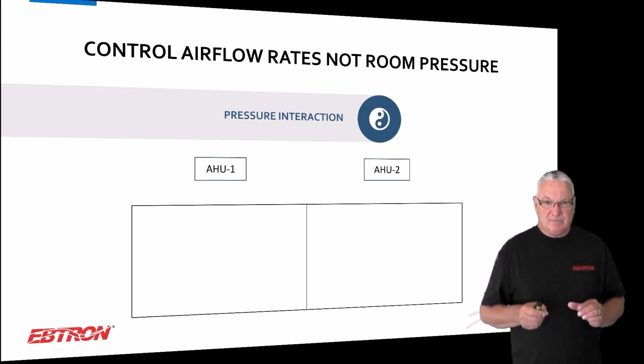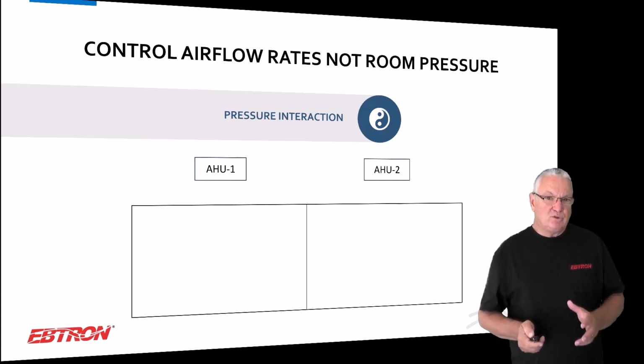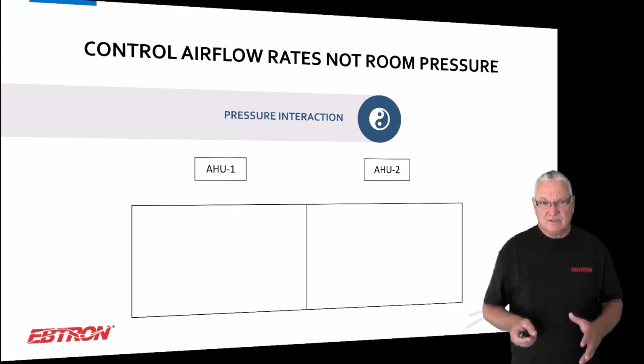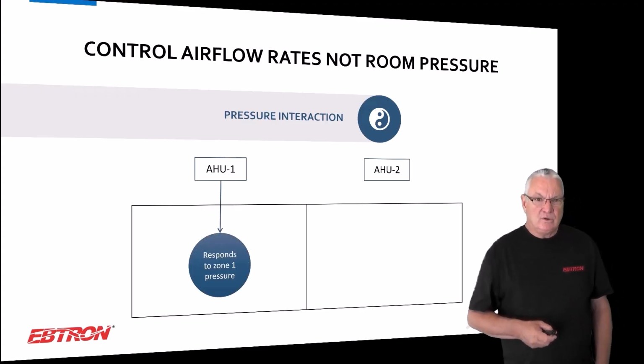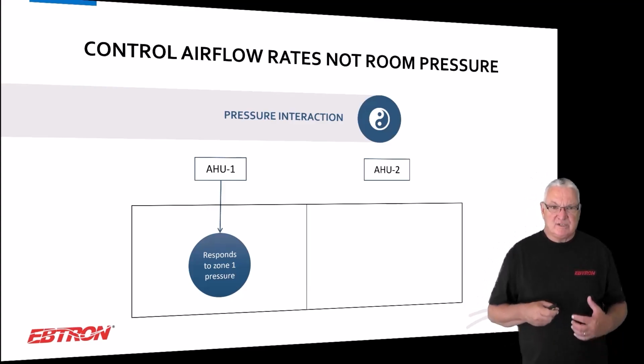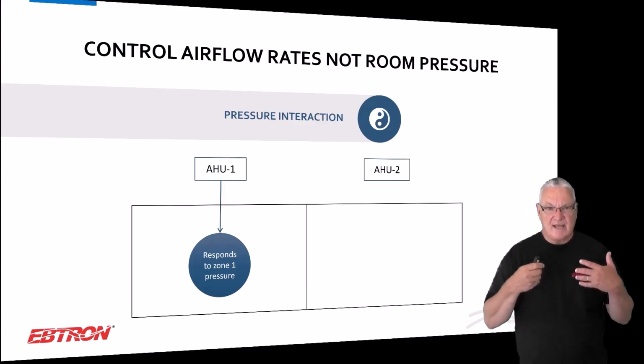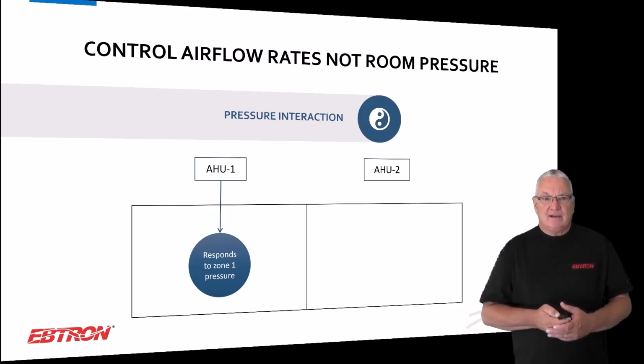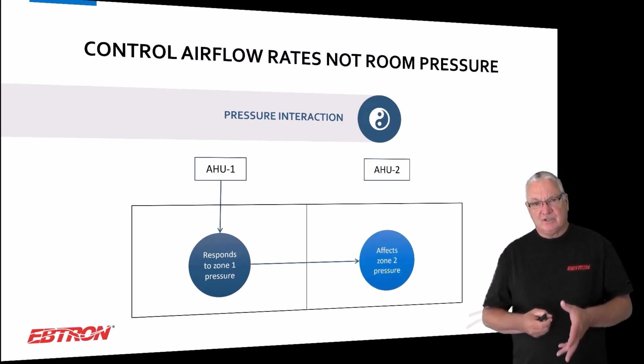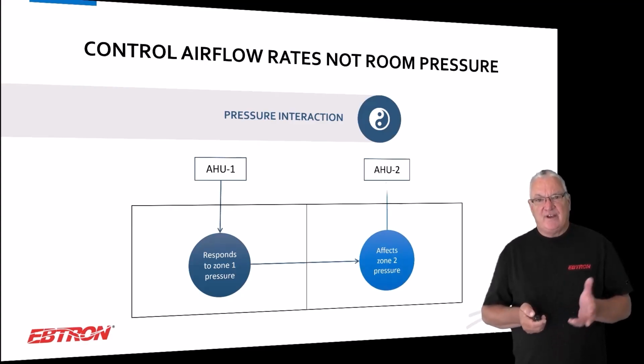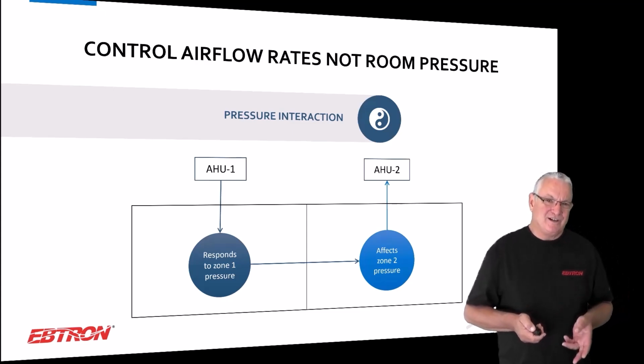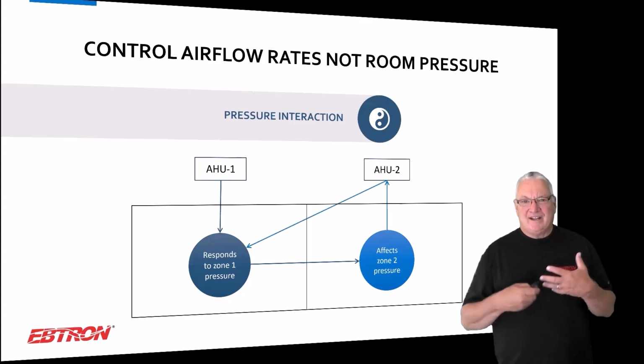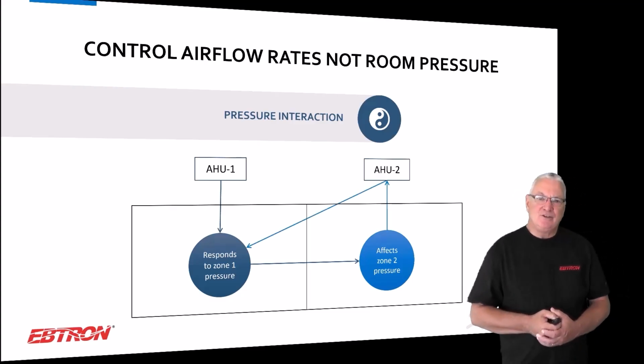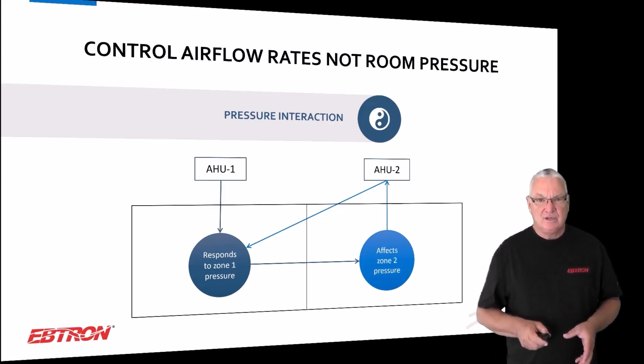one of the biggest problems when doing pressure control in healthcare facilities in particular is you might have multiple air handling units serving those two boxes or two pressure zones, so that pressure zone is responding to what that air handler is doing, air handler one. But what air handler one is doing is affecting the pressure of the adjacent zone, which then affects the control of air handler two, which then affects the pressure of zone one, and it goes on and on and on. And so what ends up happening is that you cannot compartmentalize pressure zones when you do pressure control, okay?